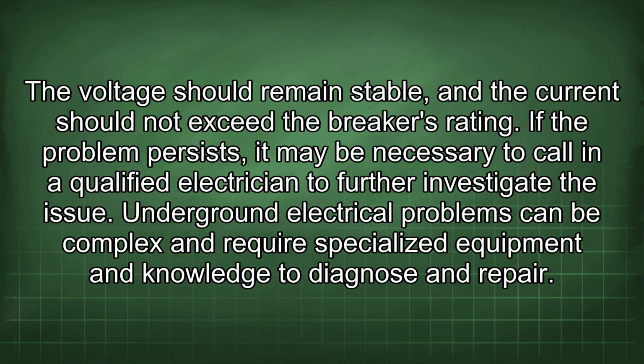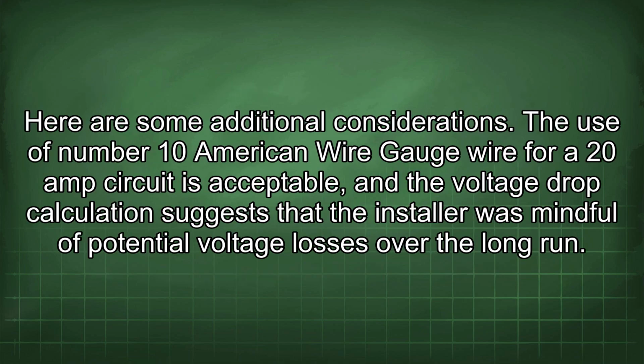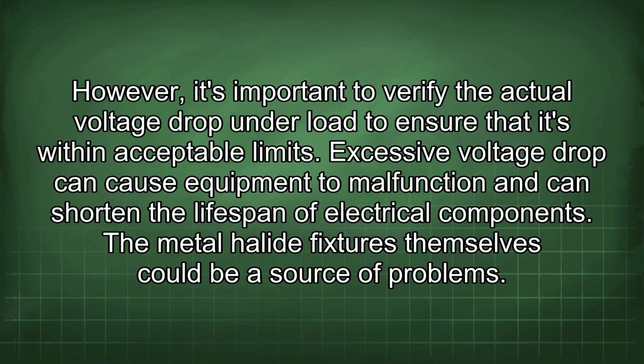If the problem persists, it may be necessary to call in a qualified electrician to further investigate the issue. Underground electrical problems can be complex and require specialized equipment and knowledge to diagnose and repair. Here are some additional considerations. The use of number 10 American wire gauge wire for a 20 amp circuit is acceptable, and the voltage drop calculation suggests that the installer was mindful of potential voltage losses over the long run. However, it's important to verify the actual voltage drop under load to ensure that it's within acceptable limits. Excessive voltage drop can cause equipment to malfunction and can shorten the lifespan of electrical components.